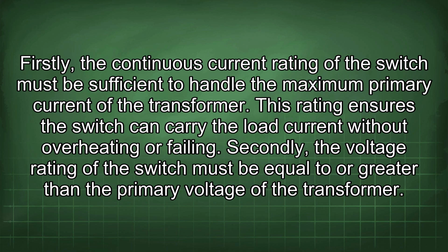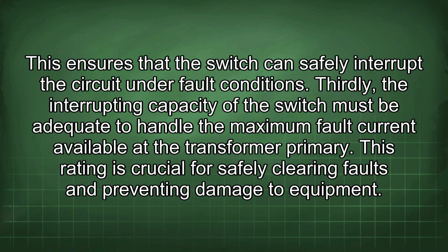operation. Firstly, the continuous current rating of the switch must be sufficient to handle the maximum primary current of the transformer. This rating ensures the switch can carry the load current without overheating or failing. Secondly, the voltage rating of the switch must be equal to or greater than the primary voltage of the transformer. This ensures that the switch can safely interrupt the circuit under fault conditions. Thirdly, the interrupting capacity of the switch must be adequate to handle the maximum fault current available at the transformer primary. This rating is crucial for safely clearing faults and preventing damage to equipment.